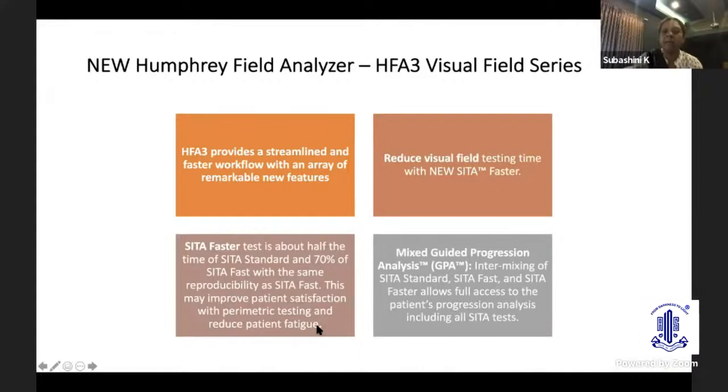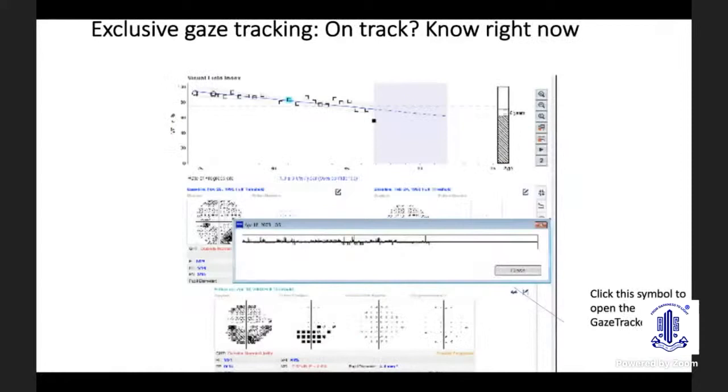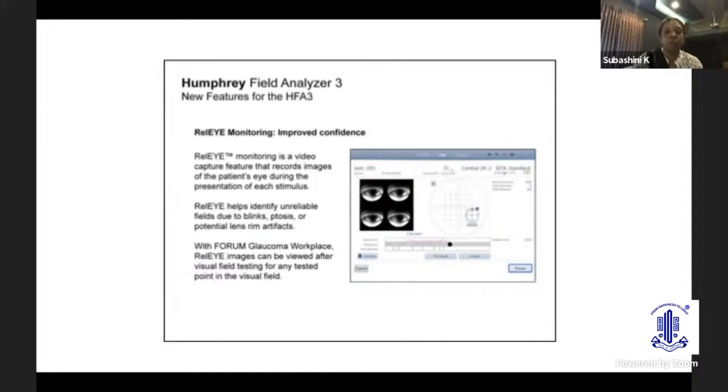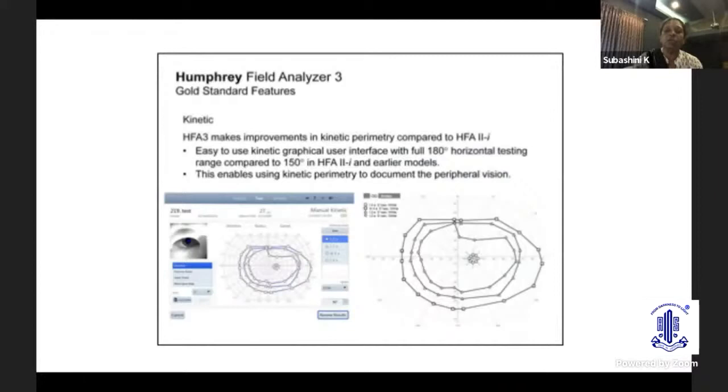The Mixed GPA allows intermixing of the SITA Standard, SITA Fast, and SITA Faster protocols, and you still get a progression analysis. Other features include exclusive gaze tracking and liquid lens technology, which automatically loads the patient's refractive correction based on the previous exam. There is also RelEYE monitoring — a video capture feature that records images of the patient's eye during the presentation of each stimulus and helps identify unreliable fields. Kinetic perimetry is also more extensive in the new HFA-3.